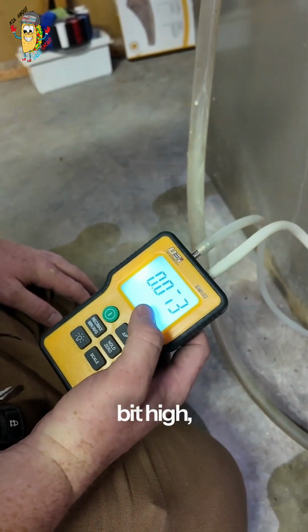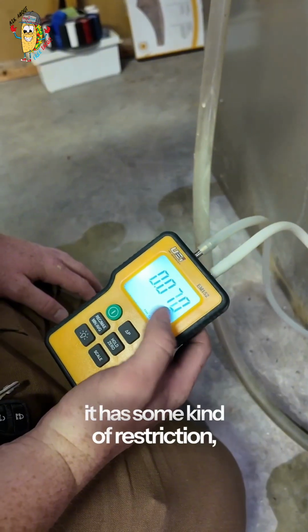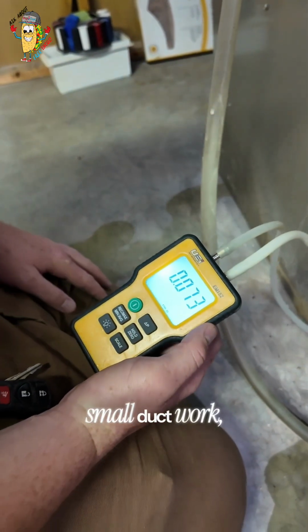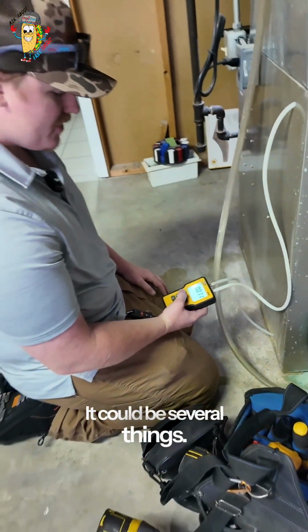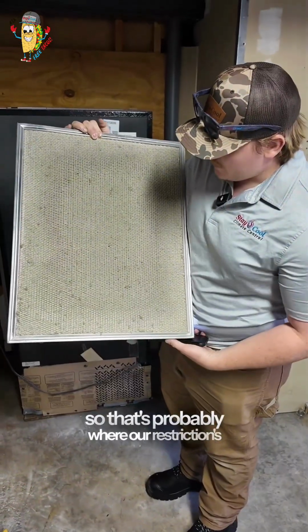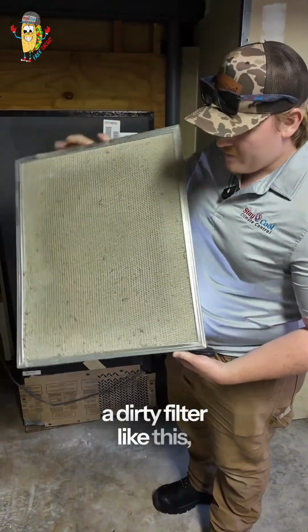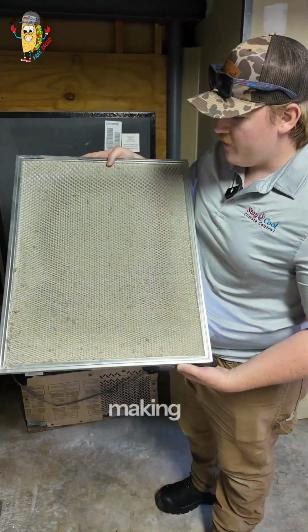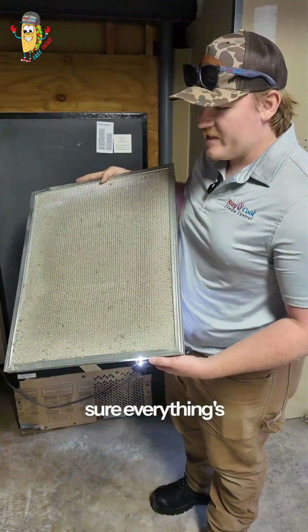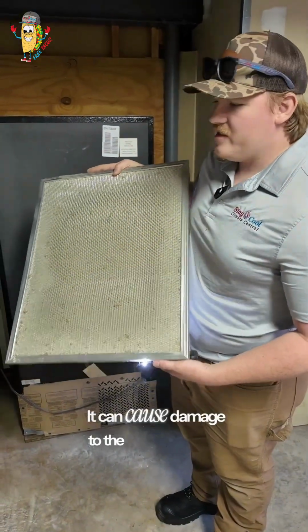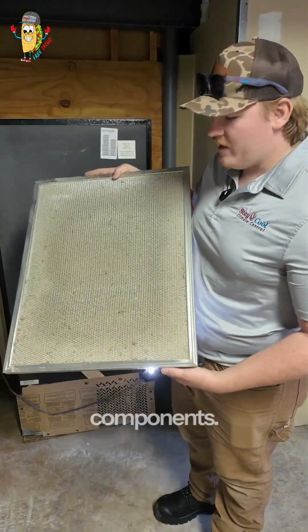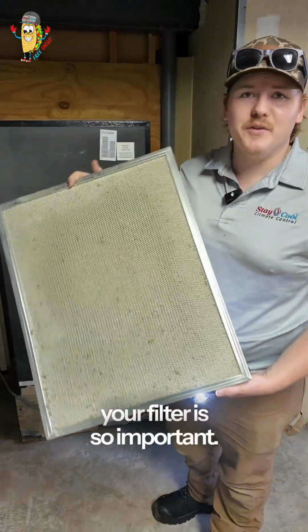This one's a little bit high, so most likely it has some kind of restriction, either a dirty filter, small ductwork, or a dirty coil. It could be several things. I would say that's pretty dirty, so that's probably where our restriction is going to be. When you have a dirty filter like this, it's going to restrict all that airflow, making the motor work harder. It's going to make everything run hotter. It can cause damage to the heat exchanger, to the furnace, and any electrical components. That's why changing your filter is so important.